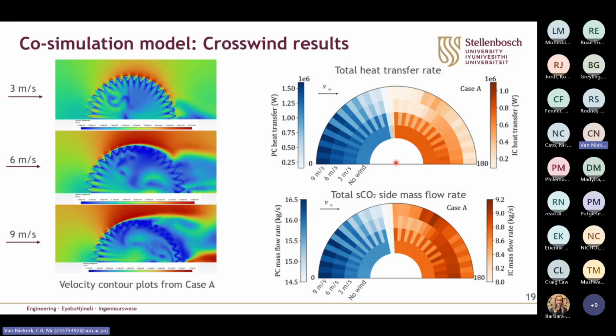So this top right figure plots the different heat rejection rates for each individual tube bank in the domain, starting with the no wind case in the inner ring and then moving out to the different crosswind velocities from there. So in this case, the blue corresponds to the pre-cooler and the orange corresponds to the intercooler. And from these heat transfer plots, we can see that the tube banks in the windward direction actually perform a lot better than the rest due to the air that's being forced over these tube banks, enhancing their heat transfer. And then we can see for the middle and leeward sectors that there's quite a significant reduction in heat transfer as the flow starts to separate and reduces the air mass flow rate and then reduces the overall heat transfer that these tube banks can reject.